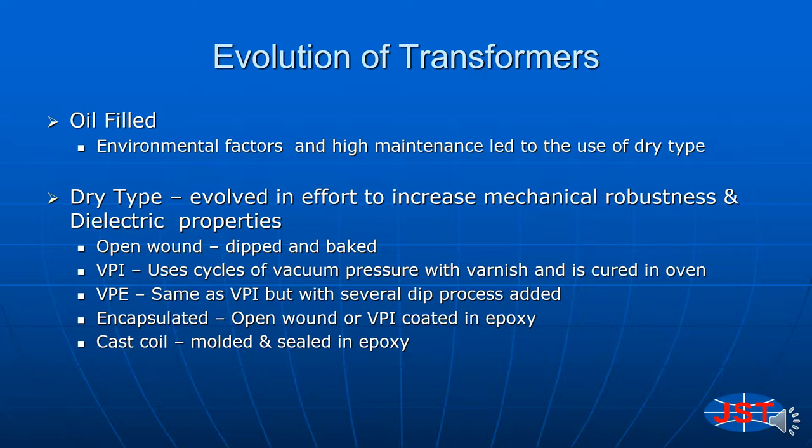Later processes were developed that would provide for a forced displacement of air trapped between the transformer windings with varnish. Vacuum pressure impregnation or VPI is one such process. VPE includes several additional dip processes to offer better protection against the elements. Encapsulated transformers are simply open wound dipped and baked or VPI transformers that are encapsulated with a protective insulating coating such as epoxy.